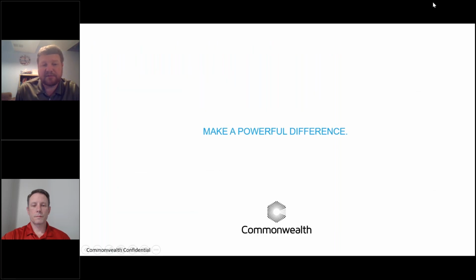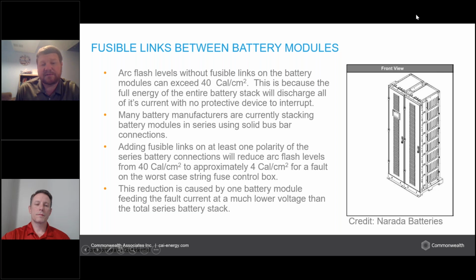Yep, and the reason this works so well is that these fusible links are separating the other batteries. You may have anywhere between 8 and 20 battery cells in series. In this way, you only have to deal with the full energy discharge of the one cell where the fault location is.